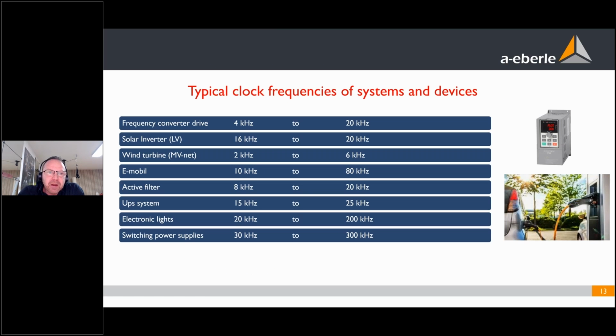Here I see typical clock frequencies of typical devices we're getting in our network more and more. For motors, we have frequency control drives. It depends a little bit on the size of your motor. If you have a big engine, then the sampling frequency of the frequency converter is low, about 2, 3, 4 kilohertz. If you have a small machine, then the sampling frequency is much higher than 10 kilohertz.